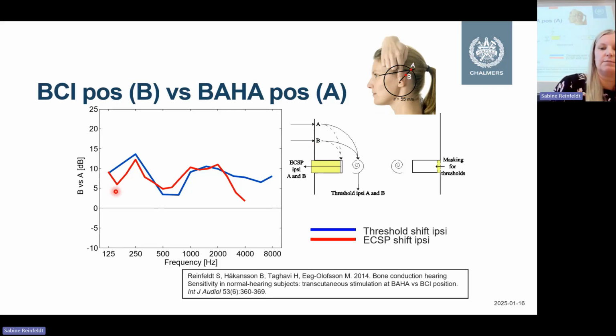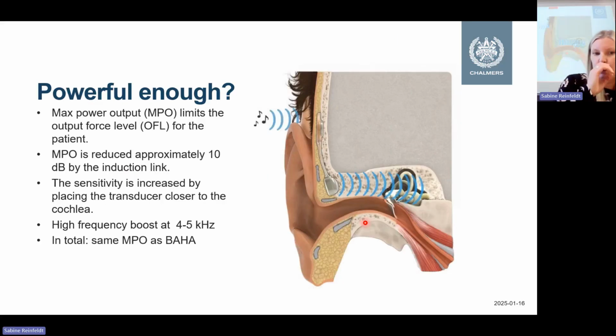And we can see the differences here, B versus A. So if it's more than 0, it means that we have a benefit for position B. So we can see that we have a benefit of about 5 to 10 decibels, depending on frequency. And we could also see that these measures are approximately the same in relative measures. And then we have also one other thing about the BCI transducer. It gives a high frequency boost around 4 to 5 kilohertz. That was not possible with the regular BAHA transducer. And together, we could see that in total, we should have the same MPO as for the BAHA. So that was good. So it should be powerful enough.